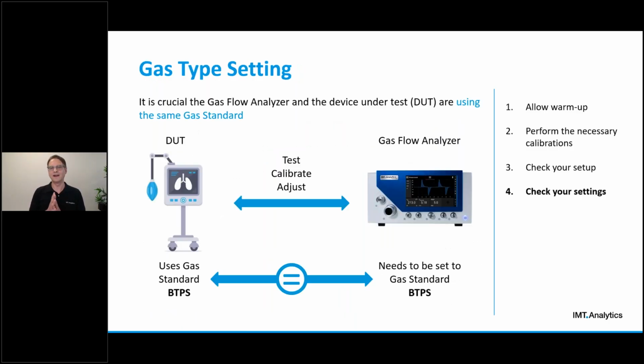So how do gas flow analyzers tackle this problem? Well, they let you display flow and volume in different gas standards. And the only thing you really need to remember from this part of theory is that the gas standard setting on your gas flow analyzer must always match the gas standard used by your device under test. In our example, the ventilator. Different ventilator manufacturers may use different gas standards. The most common ones are called BTPS, as already mentioned, and you will also see STP, for example. And the only thing you really need to figure out is the gas standard used by the device under test, and then set the same gas standard on your analyzer.